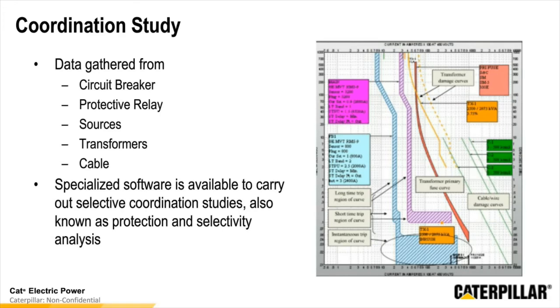So in a coordination study, and when you really are starting to do this with a full system, there's a lot of data to be gathered. You need to gather the information on your circuit breakers and the different settings that you have available to you: the long, the short, and the instantaneous trips. You need to look at your different protective relays that you may have within the system and make sure that you're taking those into consideration so that you're allowing enough current when necessary.